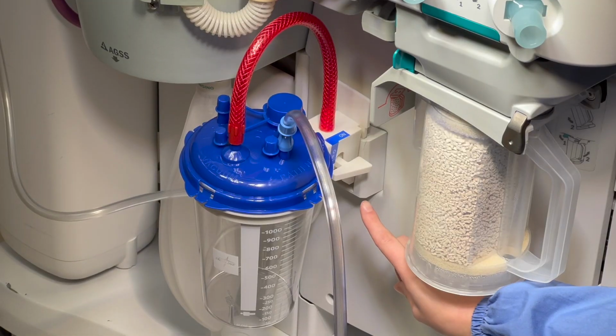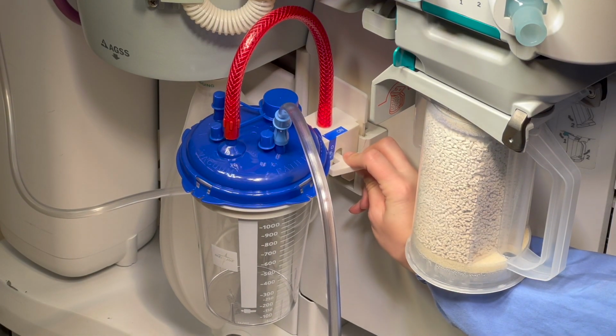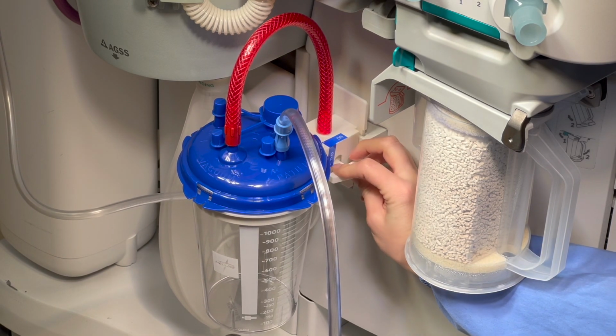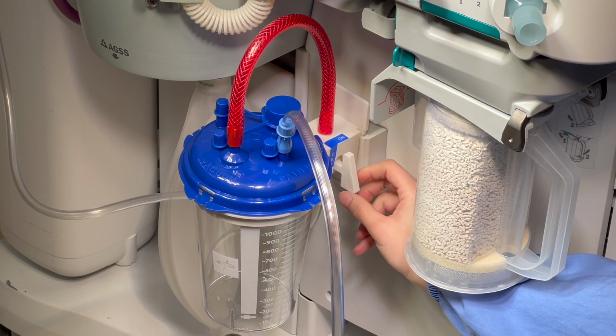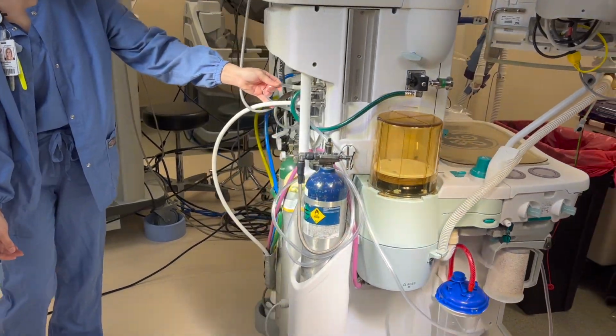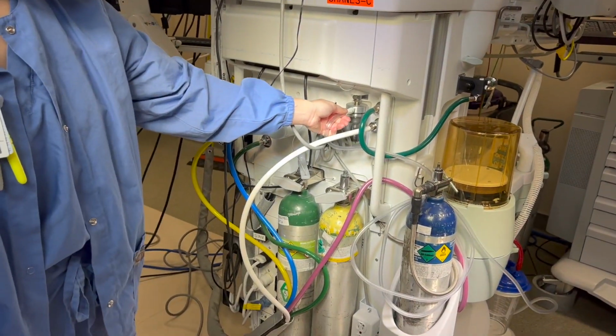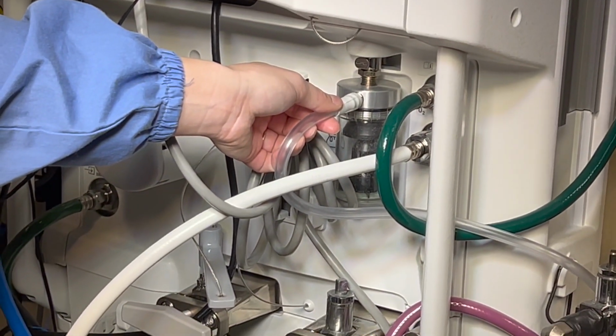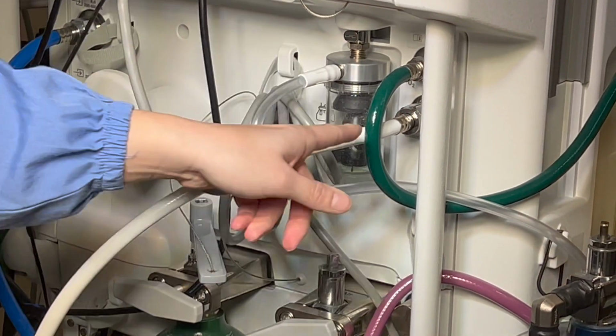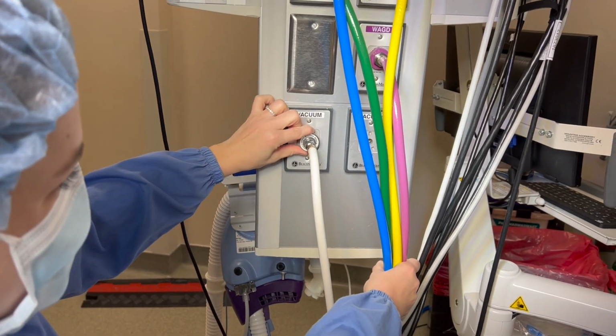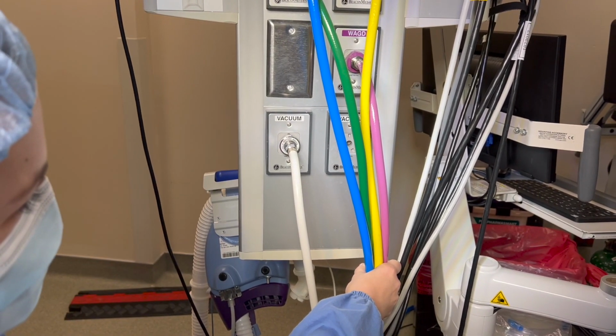And if you're having issues with your suction, you may need to turn on suction to the canister itself using the switch you see here. You can also double check the tubing that it's connected properly to the back of the machine, going from the canister to the machine, and then ensure that this white tube is properly secured and that it's connected to the part on the stand here that says vacuum. For obvious reasons, you always need to be able to clear the airway, and that's why we have suction immediately available.